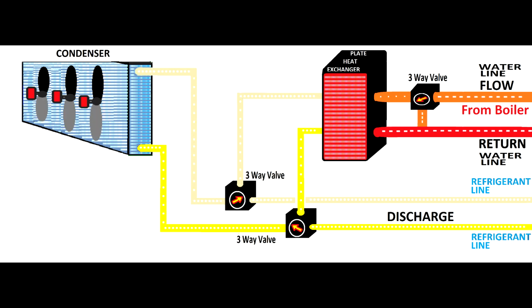If the system is not well designed and there will not be enough heat exchanging between the water and the plate heat exchanger, then as you'll see here, the refrigerant will still leave the plate heat exchanger very hot, and part of it has to be redirected into the condenser to control the refrigerant pressure.